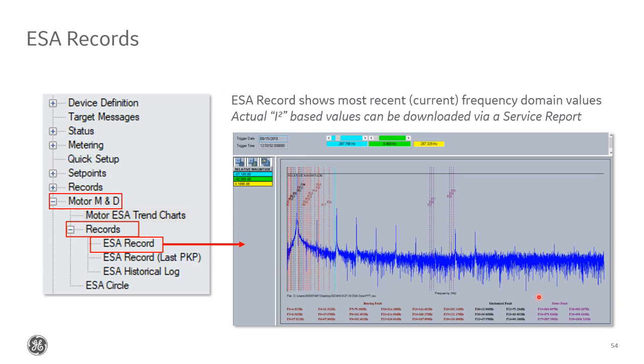I mentioned before that you can actually see the Fourier transform that we look at. This can be found, if you're online, under the motor M&D option, records, and the ESA record option. If you double click on this, it'll open the FFT window like this. Here we'll show you the FFT from the most recent calculation, again, with all the fault frequencies flagged. You can screenshot it like I did here, or you can download it in a CSV file format so that you can see the values in table format or plot it elsewhere.